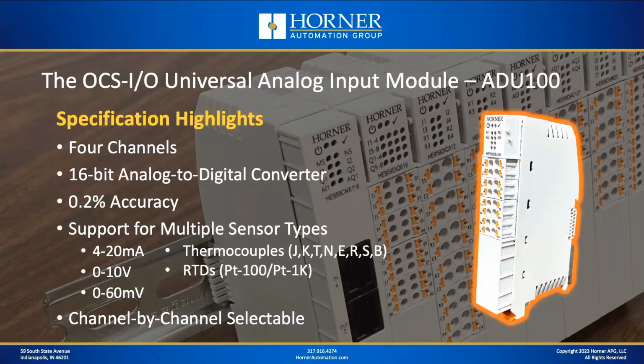All right, let's start with some of the highlights with specifications up first. There's 4 channels in the ADU 100, and it's built using a 16-bit A to D converter, which means it has plenty of resolution for most applications. It's quite accurate with a good specification of 0.2%. And as we talked about in the opening with Casey, it supports a whole bunch of sensor types from 4 to 20 milliamps or 0 to 10 volts, all the way to thermocouples, RTDs, and even millivolt signals. And as Casey mentioned earlier, one of the best things about the ADU 100 is that it is channel by channel selectable for the sensor that you're going to use, which makes it extremely versatile and economical.